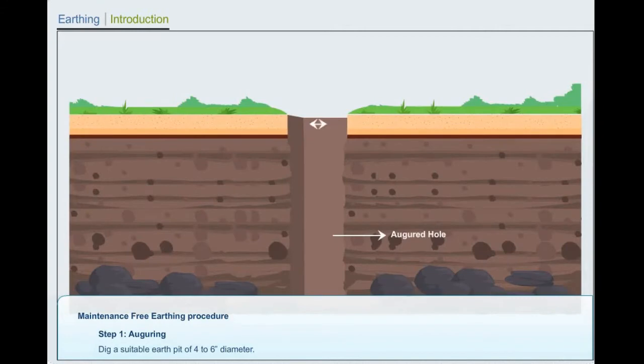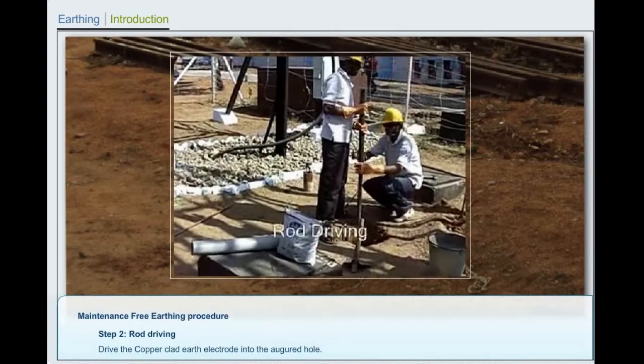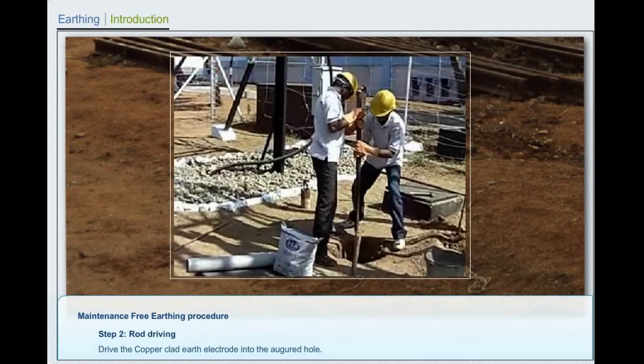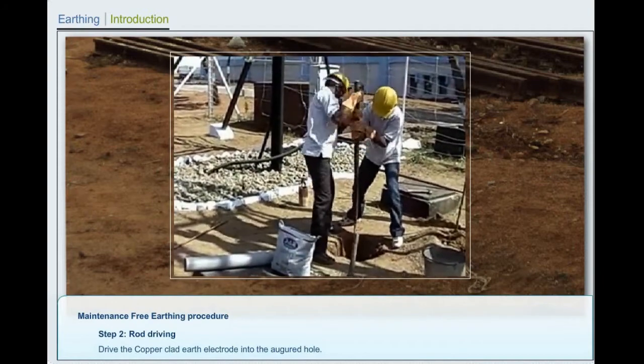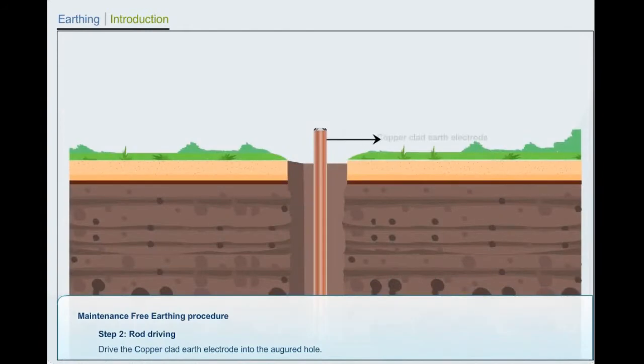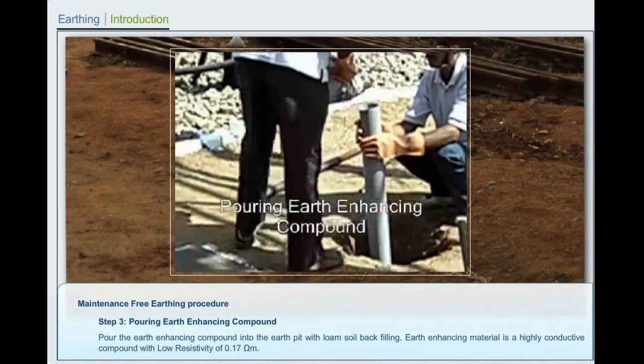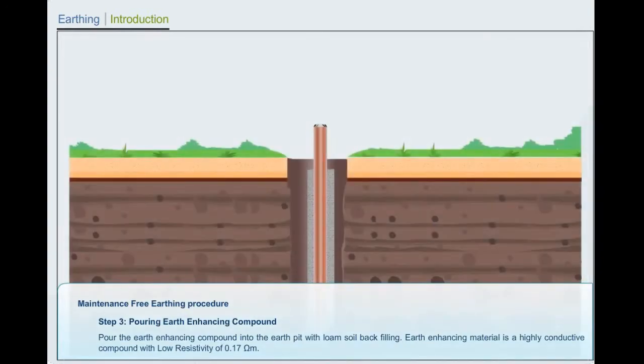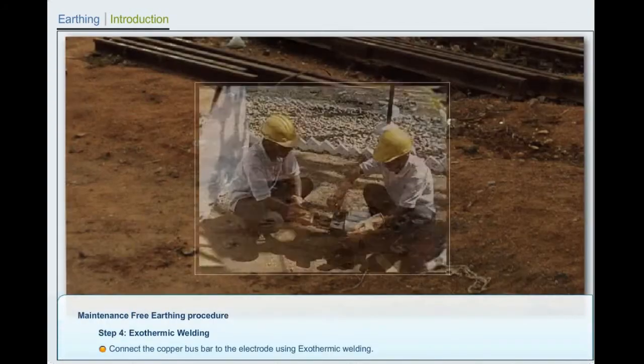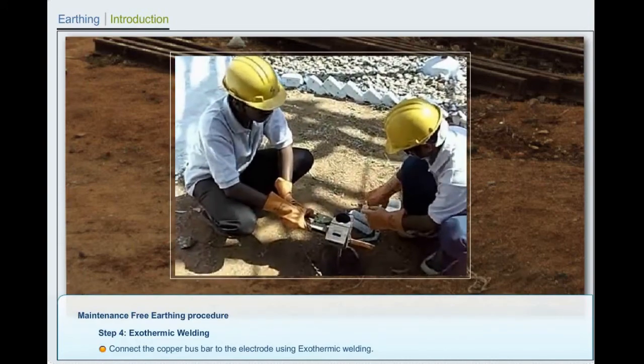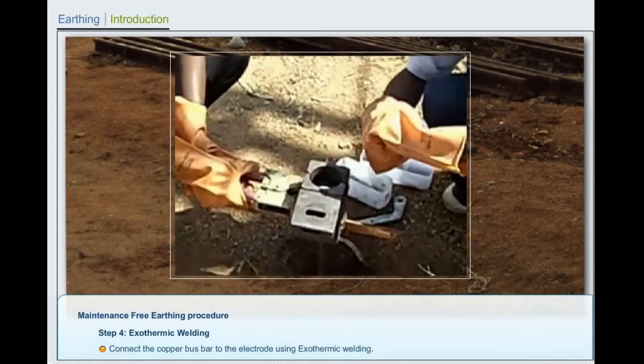Step 1. Augering. Dig a suitable earth pit of 4 to 6 inches diameter. Step 2. Rod driving. Drive the copper-clad earth electrode into the augured hole. Step 3. Pouring earth-enhancing compound. Pour the earth-enhancing compound into the earth pit with loam soil backfilling. Earth-enhancing material is a highly conductive compound with a low resistivity of 0.17 ohm meters. Step 4. Exothermic welding. Connect the copper bus bar to the electrode using exothermic welding.